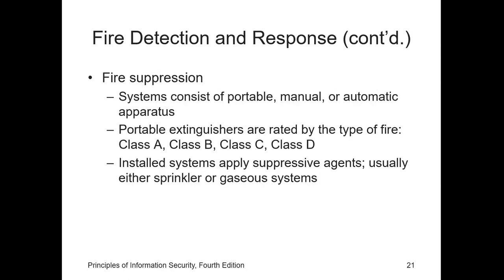Class A fires use water and multipurpose dry chemical fire extinguishers. Fires fueled by combustible liquids or gases such as solvents, gasoline, paint, liquor, and oil — class B fires — use carbon dioxide, multipurpose dry chemical, and halon fire extinguishers. Class C fires involve energized electrical equipment or appliances and use carbon dioxide, multipurpose dry chemical, and halon fire extinguishers.